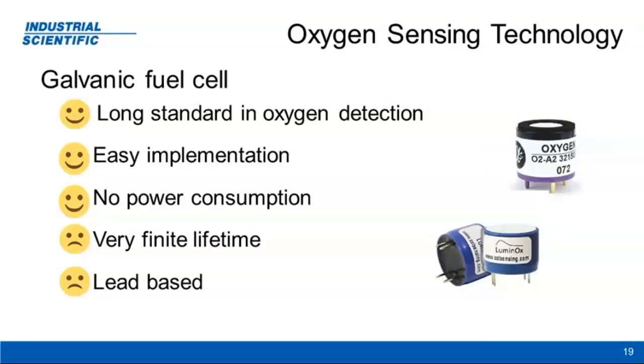But on the downside, galvanic fuel cells are lead-based, and because of that they have a very finite lifetime. Once the lead in the sensor is consumed and converted to lead acetate, the sensor's dead. That lifetime is very finite based on the output of the sensor, and the end comes very quickly—they die catastrophically, with very, very little warning.